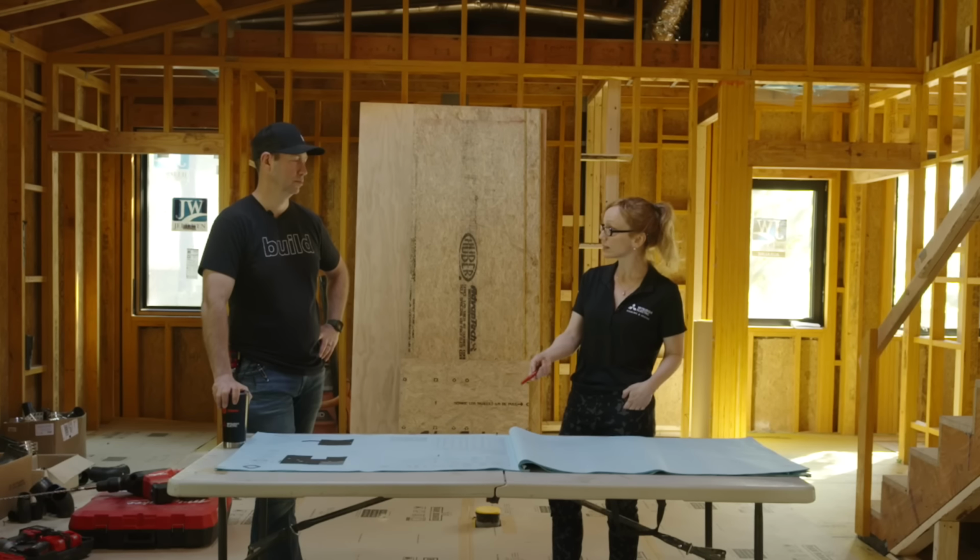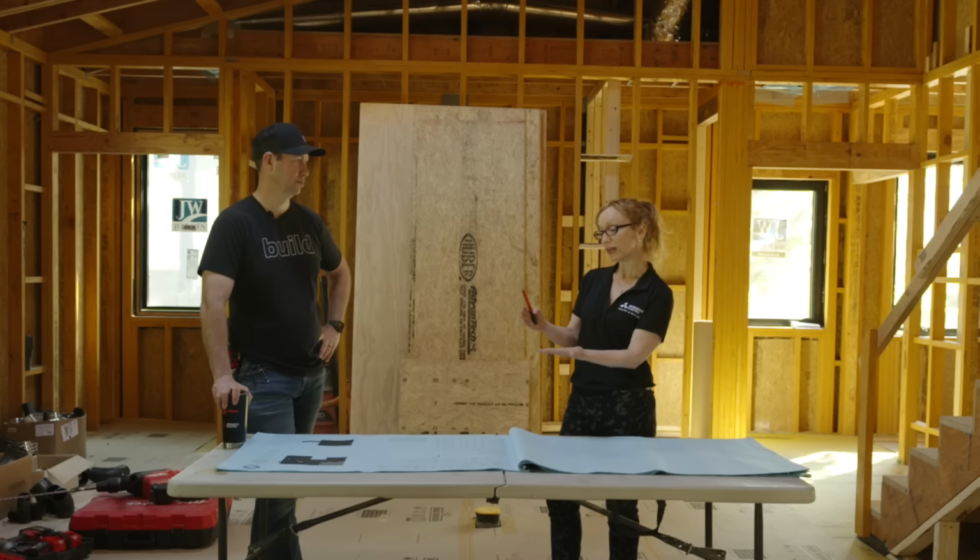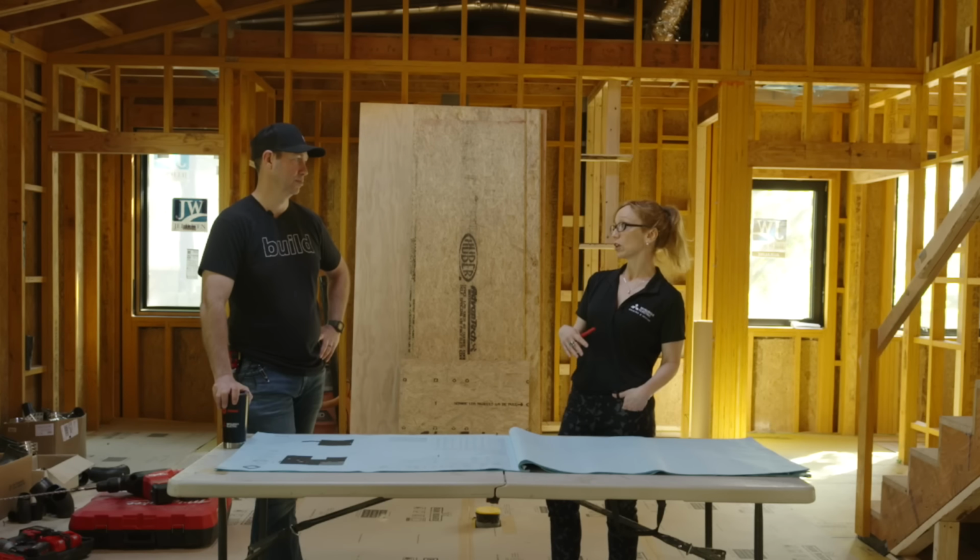So in the case of this system that you've got, 48,000 BTUH or 4-ton outdoor unit, we can ramp down in cooling all the way down to a third of that overall tonnage. That's amazing. And in heating, it's even lower than that.